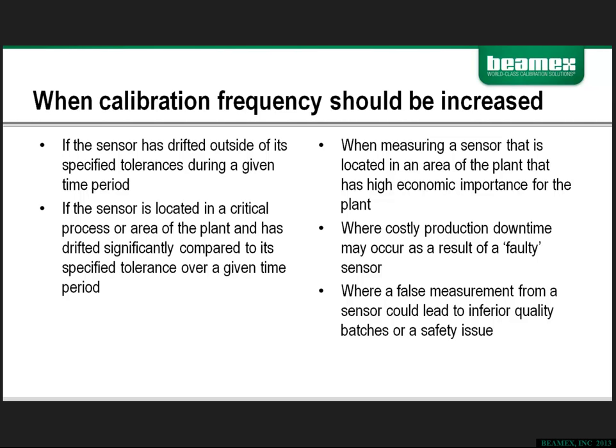Sometimes industry regulations may give you some guidance when it comes to doing that, but the best rule of thumb is to look at it on a structured basis. Look at it first as, I'm going to look at this particular manufacturer and model number of device, and then from that I'm going to evaluate all of those devices to make sure that there aren't a couple in there that are drifting worse than all of the others. And that would help you identify also which ones would need to be replaced on a more frequent basis than the rest.